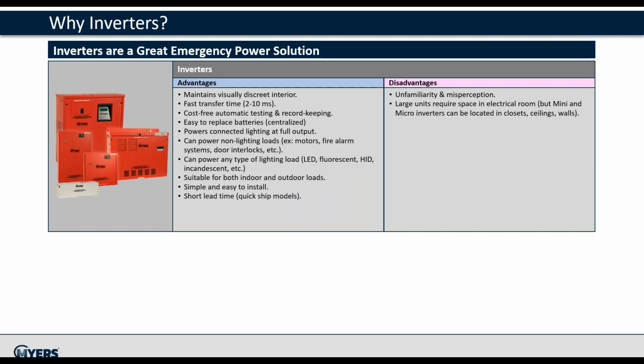Inverters have the advantage that the interior is visually unchanged. The system is a fast transfer. There's no cost for testing or record keeping. There's a single area for battery replacement.